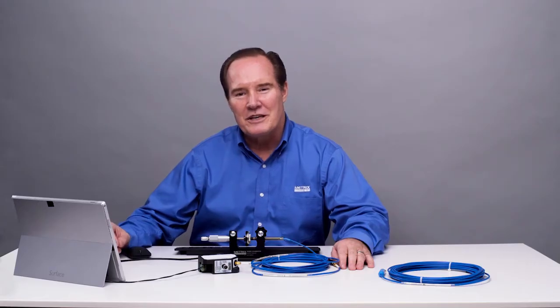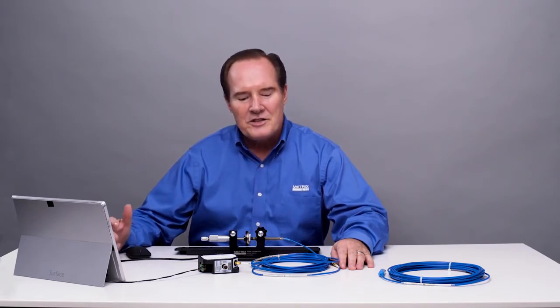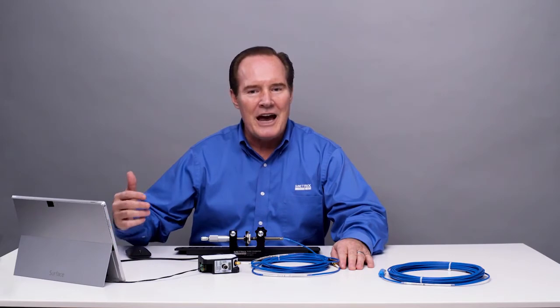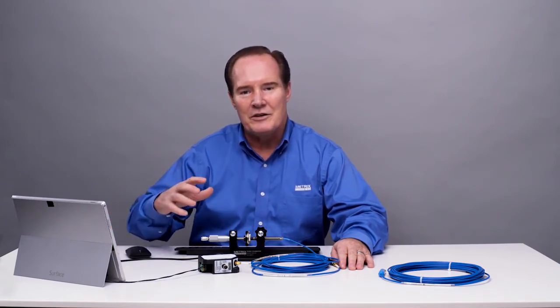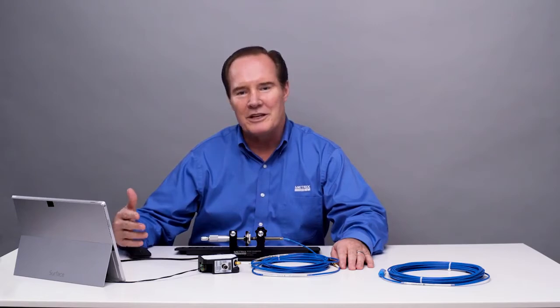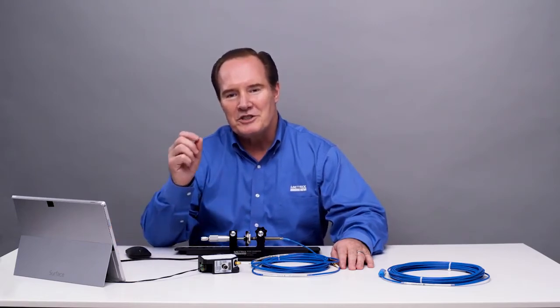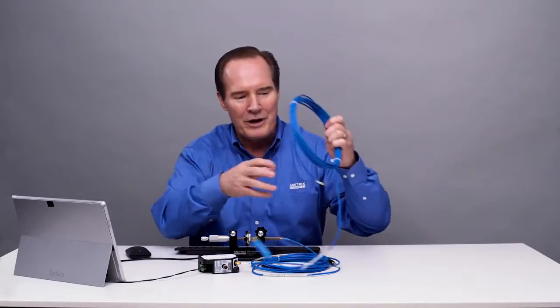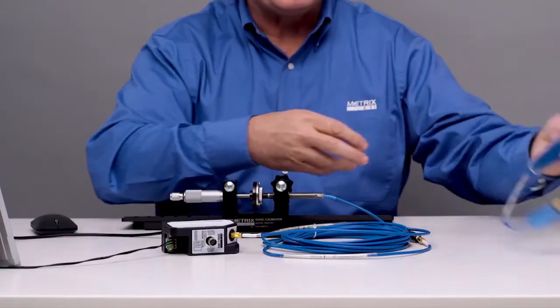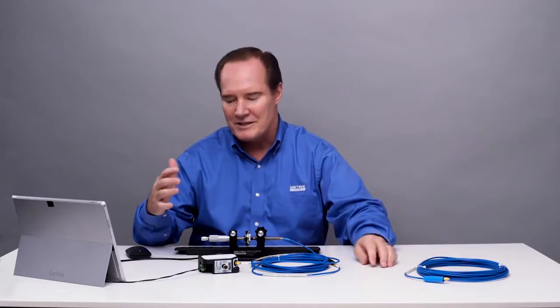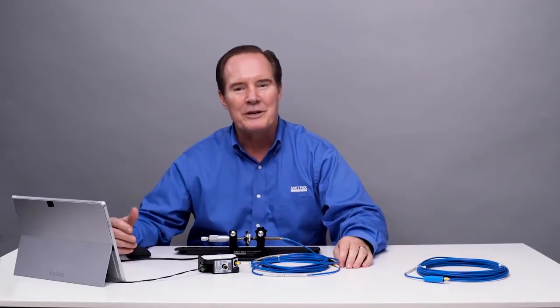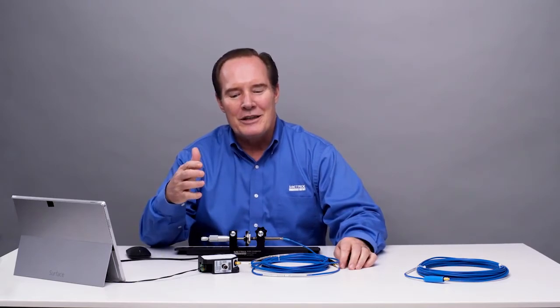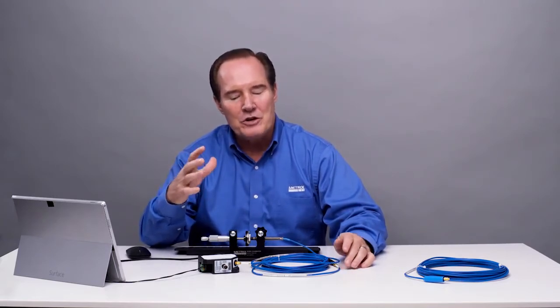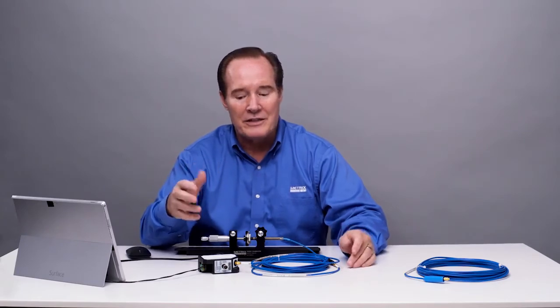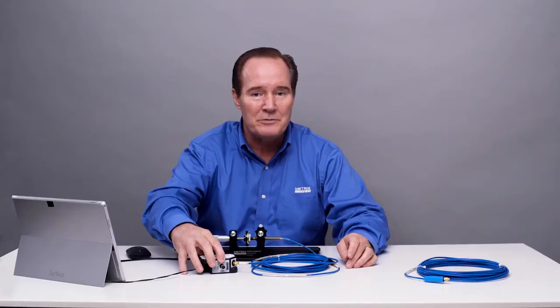One of the nice features of the digital proximity system is the ability to adjust system length. This comes into play when you're using, let's say, a 9-meter system or a 5-meter system, and you choose the system, make sure you have enough cable to get to the junction box. But what you discover inside the junction box are these coils of cable that are wound up, just in excess in that box, and it creates a little bit of an aesthetic problem. It's one of those things that you don't open up the panel because you don't want to show anybody, but it becomes unsightly. Well, you usually have to keep that 9 or 5-meter system length in order to get the digital proximity system to work.